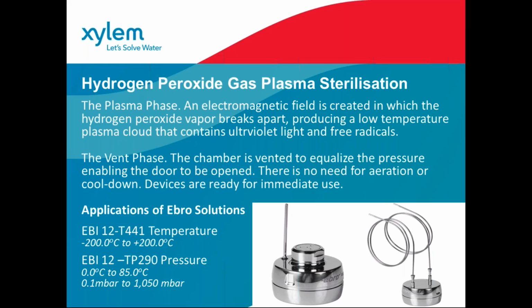of one cycle. So you must remember that applications for Ebro solutions for this are very specific, only for H2O2 sterilization. That's because of the requirement of one logger to measure very low pressure. And we have a solution for that with the EBI 12 TP290, because it is very accurate as well, measuring at very low pressure.